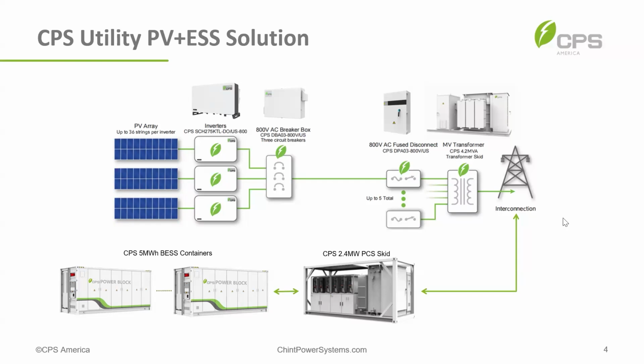But the main thing I want to point out here is that point of interconnection, which I alluded to a few minutes ago when talking about some pain points people are seeing. Those pain points were the transformers. So with our PCS skid, you get a built-in transformer, and that transformer can be 12 kV to 34.5 kV—whatever you essentially need it to be, we can make it.